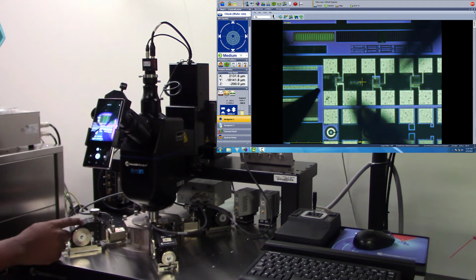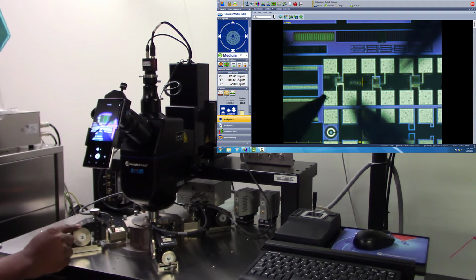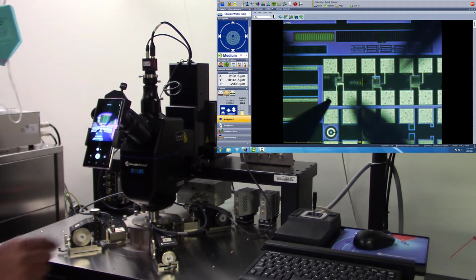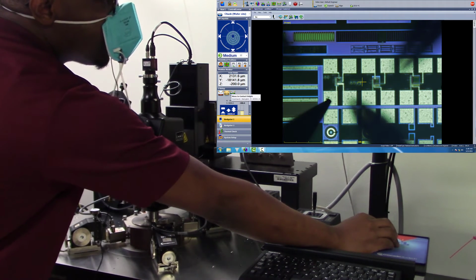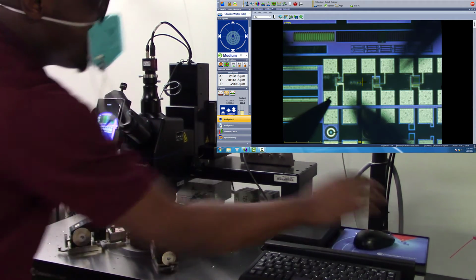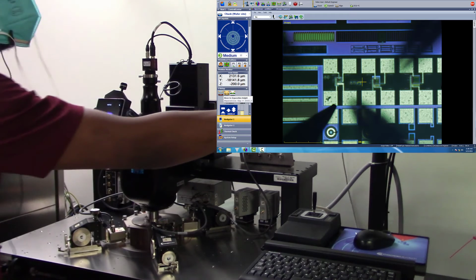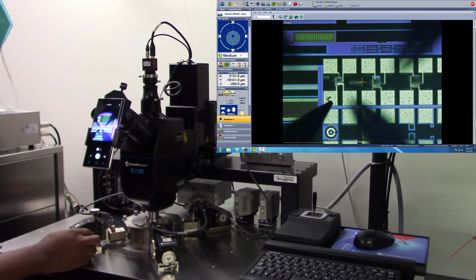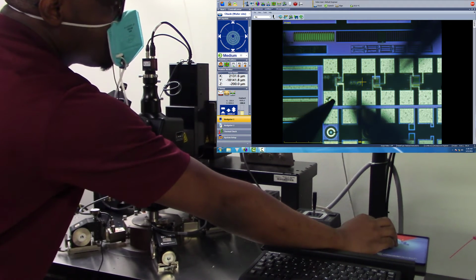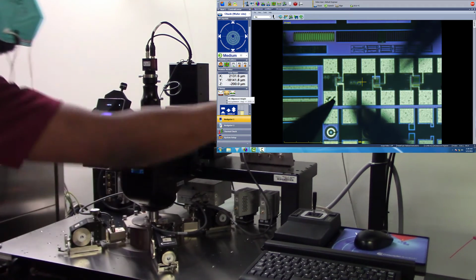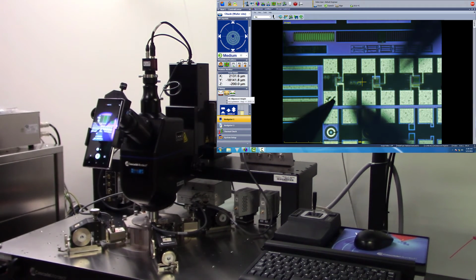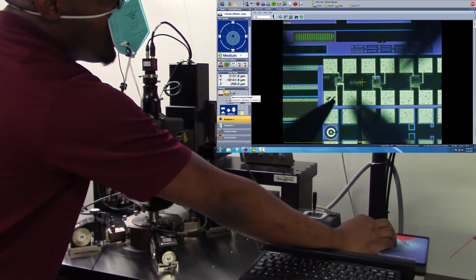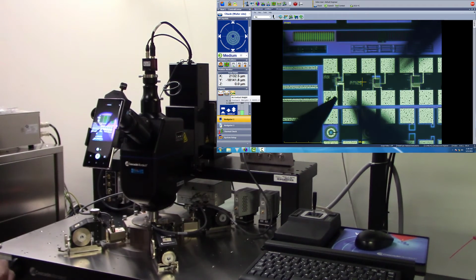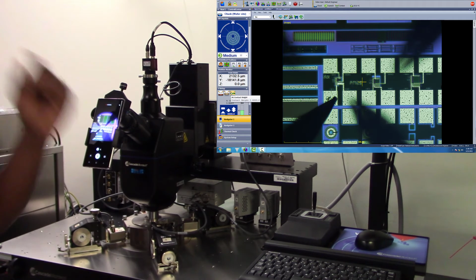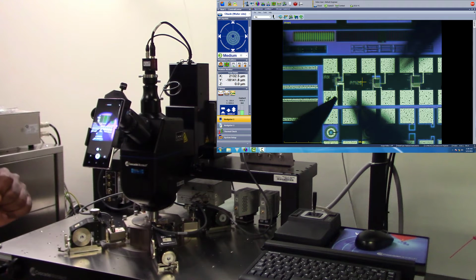So what I'm going to do now is bring back this probe tip onto my device, and I go back into contact mode and verify again. You will see that you should have a scratch on your device, just like we said earlier on. If I move it to another position on my device and go back into contact mode, I should be able to see that same scratch on that device. So that is how you simply land a probe tip on any device you want, and that way you have good contact between the probe tip and the device you want to measure.